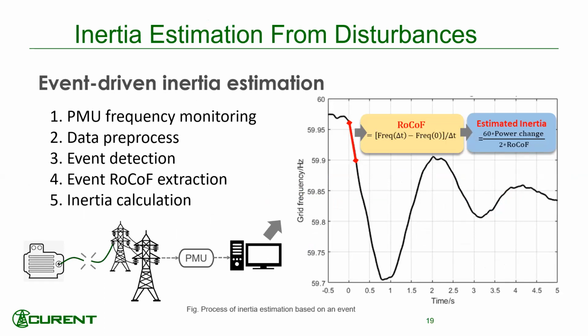You use the slope, or ROCF, rate of change of frequency, because your slope or ROCF is proportional to 2 things. One is the system inertia, and one is how much generation is lost. And this is a generator trip case. So if you know how many megawatts are lost, and you know the ROCF from measurement, you can calculate system inertia. As you know, there are many other secondary processes that affect this number. However, this is the major dominant factor determining ROCF in a grid. So it's quite easy if you constantly have large disturbances like this.